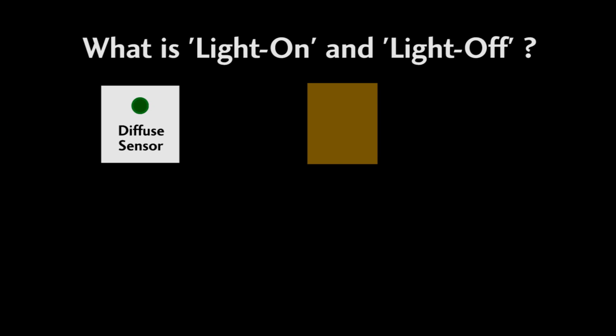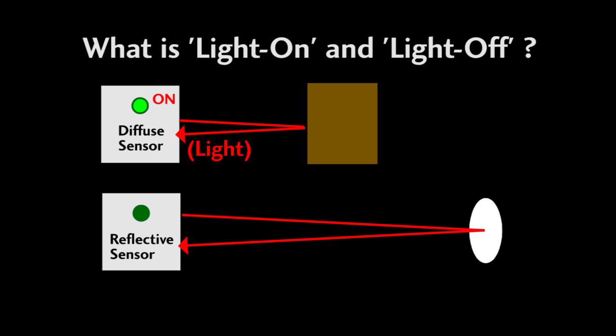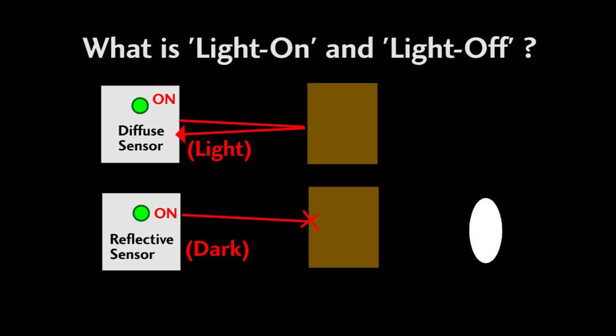A diffuse sensor is normally light-on since its output is on when its own light source is reflected from a target. Reflective and through beam sensors are normally dark-on since the output is active when the light beam is blocked.